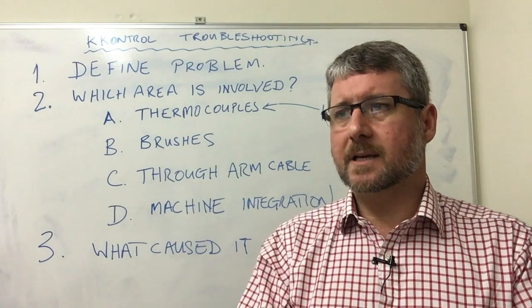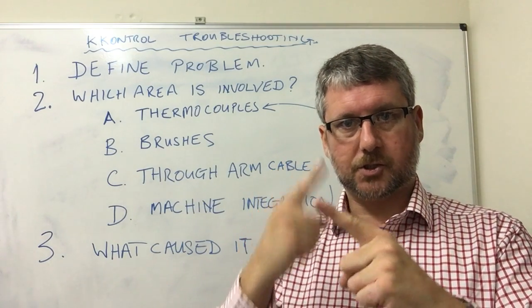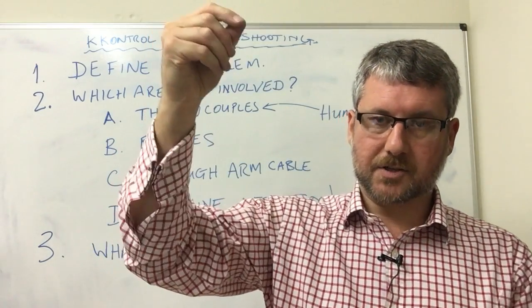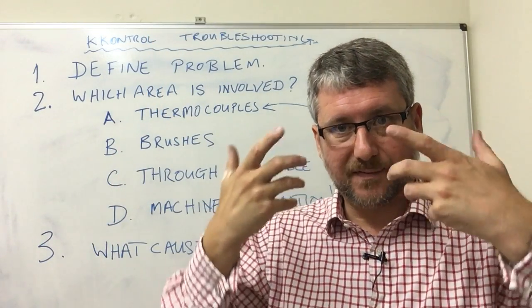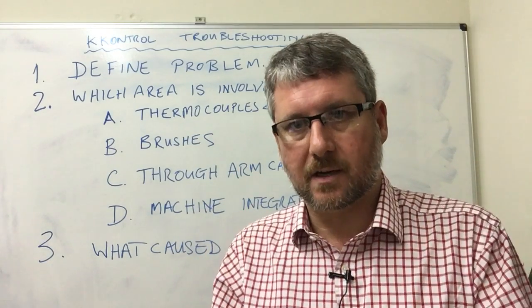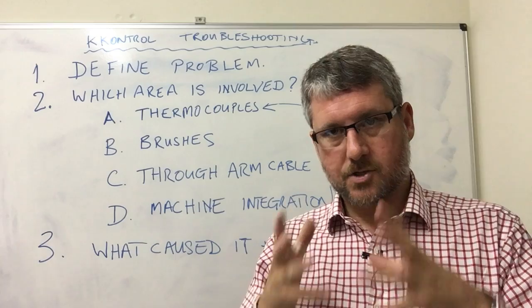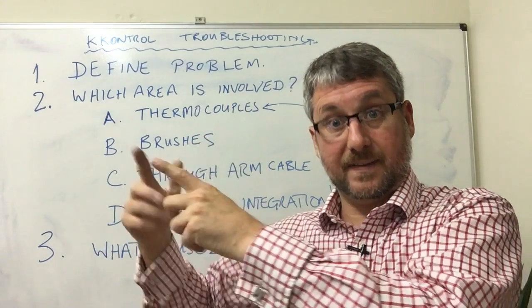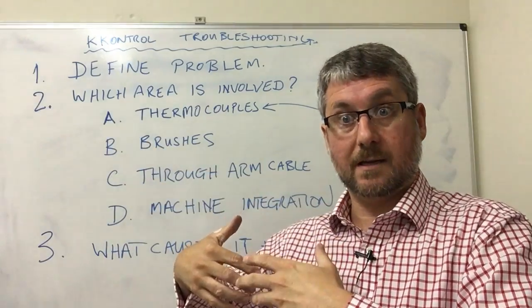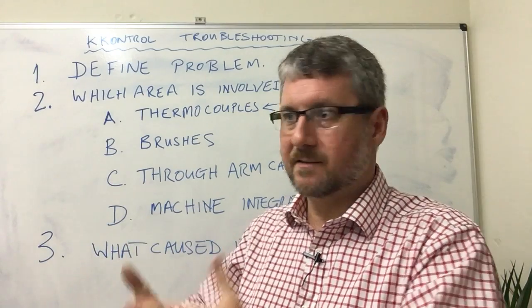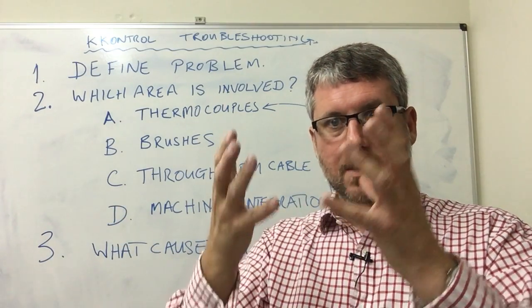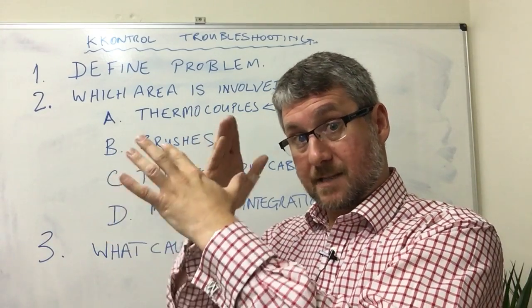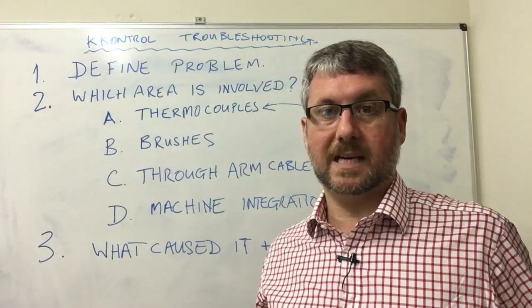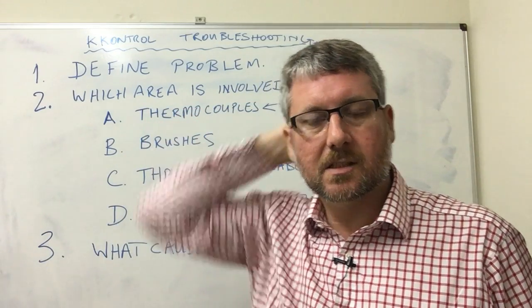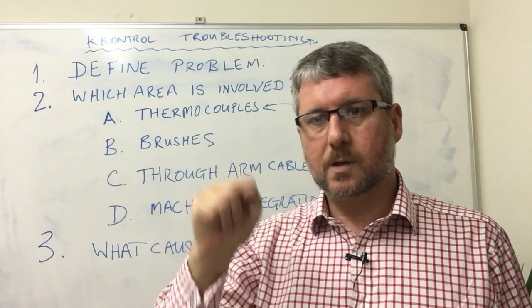Why a minimum time? Because again, as I already said, when the thermocouple is short, it faults to a high temperature. So the chances are that if you're going to fail, you're going to fail by taking it out of the oven prematurely. So in the cooling side, if it fails, it's going to also bring it out prematurely because it's cooling down. You're looking for the temperature to fall to 100, 110, 90, whatever you have decided is best for your process. It's shorted, it's measuring the ambient temperature, it has dropped below the 110, the machine says cycle is finished. But we need to compare the temperature with what the time should be.